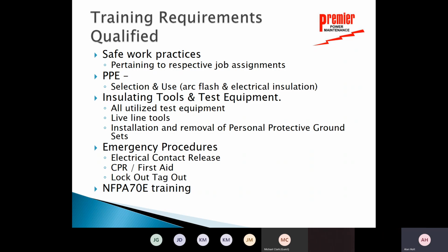Now, you also need to be knowledgeable of the live line tools. We talked about that. And you need to be trained and knowledgeable in the installation and removal of temporary protective grounding equipment. Now, I don't know whether we install any more grounds at the Marathon facility. Normally they did that, but we'll talk a little bit more about grounding in just a little bit. So, Hey Alan, just to let you know, they still pretty much apply all the grounds and stuff unless we decide we want personal protection beyond theirs. We ask, and a lot of times we get that permission and we can do that.